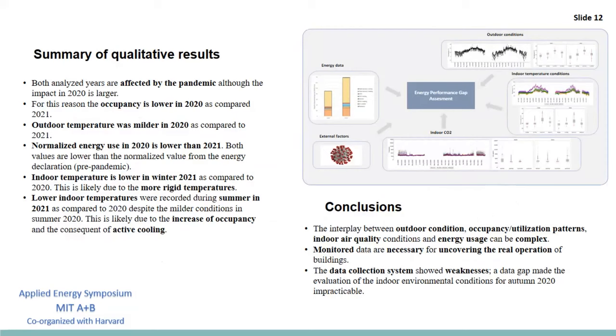Both analyzed years are affected by the pandemic, although the impact in 2020 is larger. As a consequence, the occupancy is lower in 2020 as compared to 2021. Another thing we see from the data is that the outdoor temperature was milder in 2020 as compared to 2021. And of course, both of these factors affected the energy use. We can normalize the energy use with the degree days method to compare years with different weather conditions. And normalized energy use in 2020 was lower than the one in 2021. And both values were lower than the normalized values from the energy declaration, which was pre-pandemic. And further work will be necessary to evaluate the performance in the upcoming years as the buildings get back to normal usage.